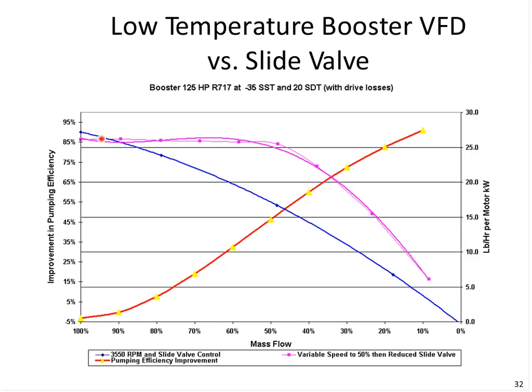So here's the slide valve performance versus variable speed. You notice even here at 50% load, we're seeing almost 50% energy savings of variable speed versus slide valve. Very interesting application here. So there we have it. Some good energy savings can be attained.